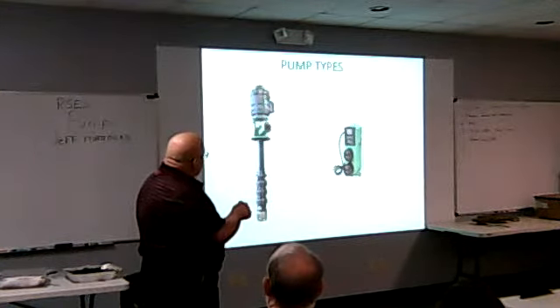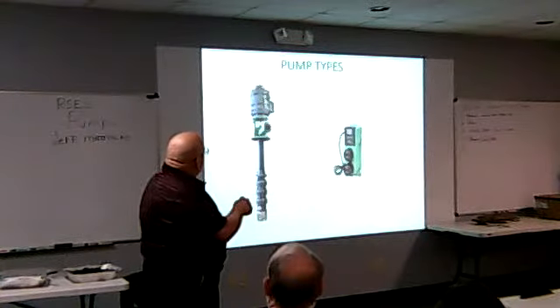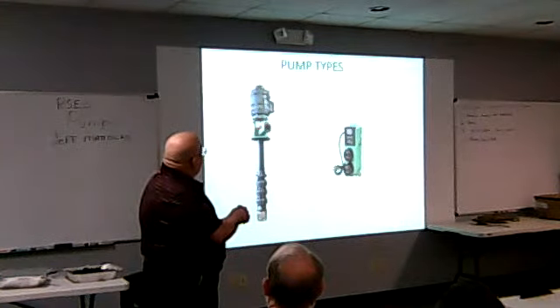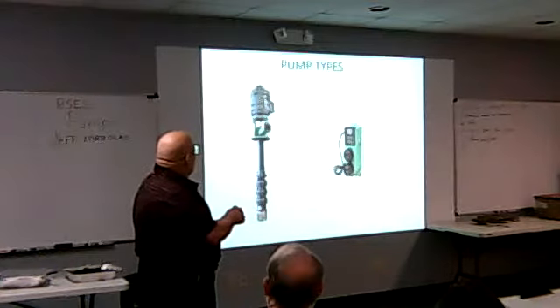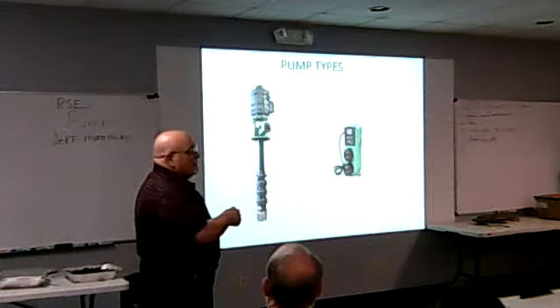These are vertical, typically they're hollow shaft motors. There's a shaft that actually slides down into here and ties into the pump. So if you need to take the motor off, you can take this coupling off, pull the shaft and take the motor off.